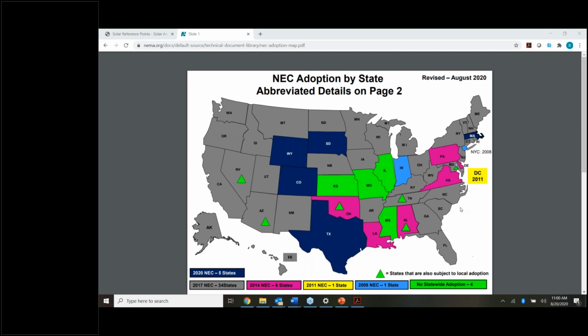The 2017 code has a lot more information, and is a more pared down version of Article 690 for PV systems. Article 705 is very, very similar. So the interconnection part, the part we just talked about with circuit breakers and all that, how it interconnects to the building, that's all virtually identical between the 2014 and the 2017. Because the 2014 code, I was very involved in the rewriting of those requirements, and that was probably the biggest benefit of the 2014 code, was getting those interconnection requirements really well nailed down.